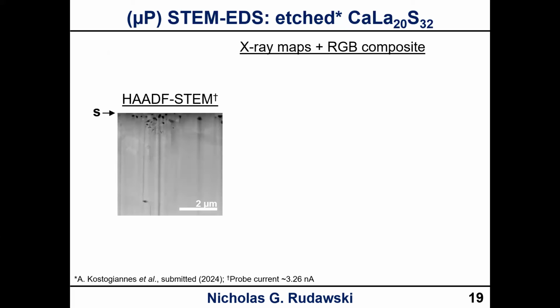So here's an example of this. This is Microprobe-STEM EDS, so this isn't just for imaging. You can do this analytically as well. And this is one of the areas where it really shines, in my opinion, is using it for analytical work. If you're doing any kind of analytical work, chemical mapping, EDS, EELS, that's in the microscale, you really have no need to do this in nanoprobe. There's really no reason why you would want to use anything but microprobe.